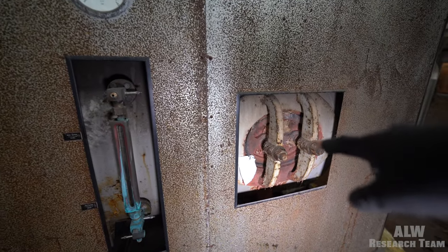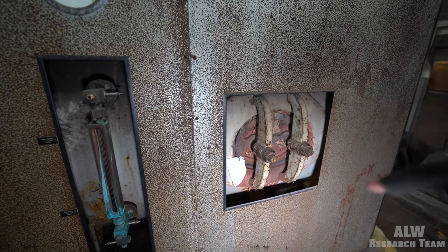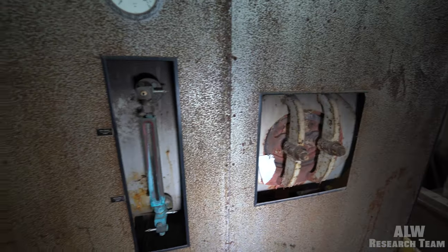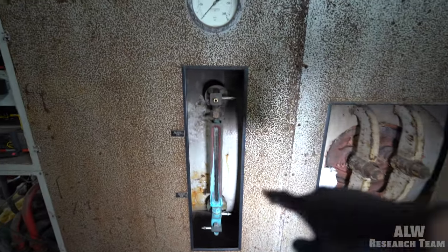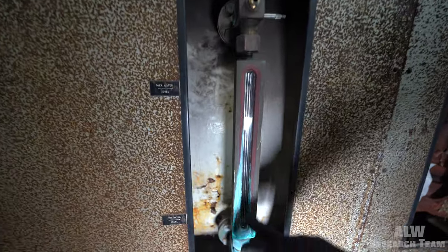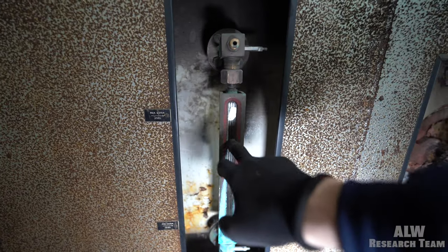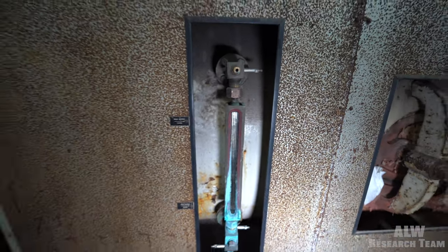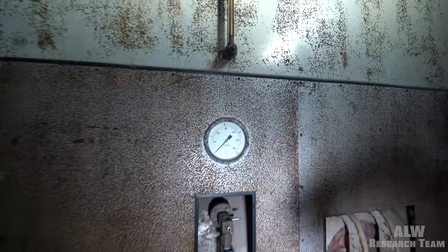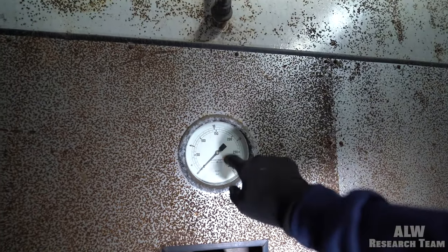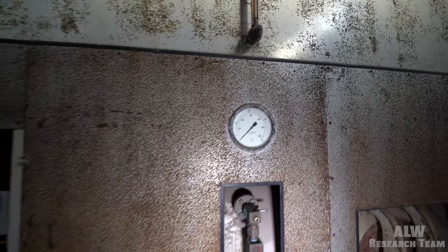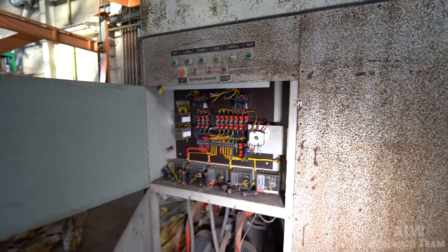This looks like a chilled water system or a heating system. That's the expansion vessel, and that's the expansion vessel header. So there would have been a water level in here and then compressed air on top to pressurise the system. There's your air pressure, or correction air—well, it's the air pressure and the pressure of the water. Little control system there.